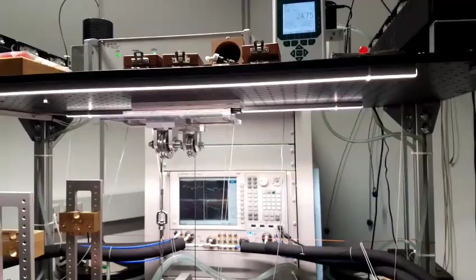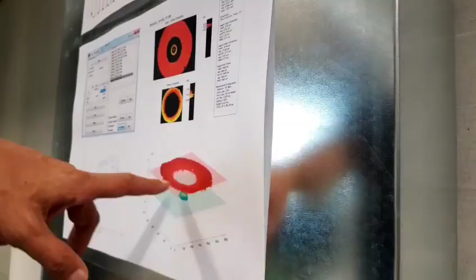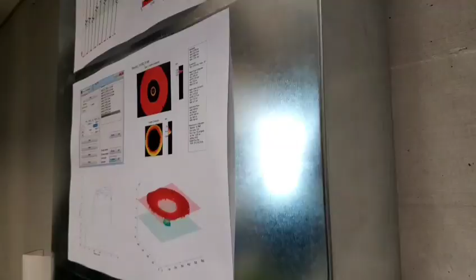You can put a connector underneath, and this is a device which can very accurately measure the distance between different planes in the vertical direction. What you see here is the inner conductor of the coaxial connector, and this is the outer conductor, and you can see the difference. This is the pin gap here, and here again the outer conductor. You can determine a mean value of the surface height, and for the inner conductor also a mean value of the height. From the difference, you know what the pin recession, or the pin gap, is.